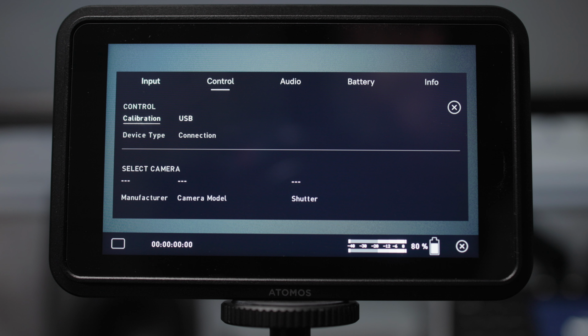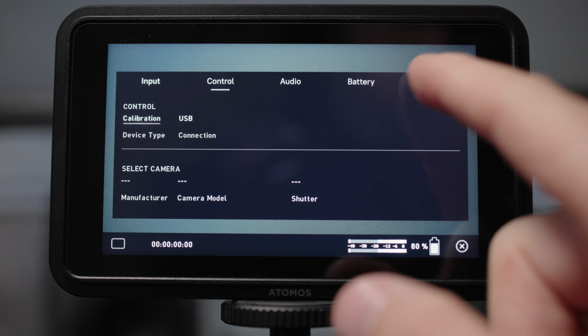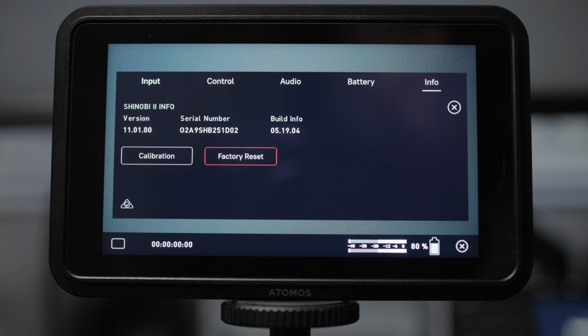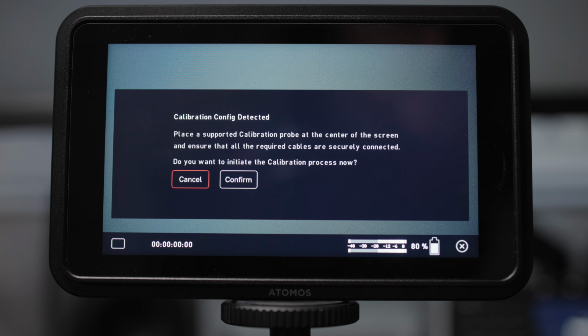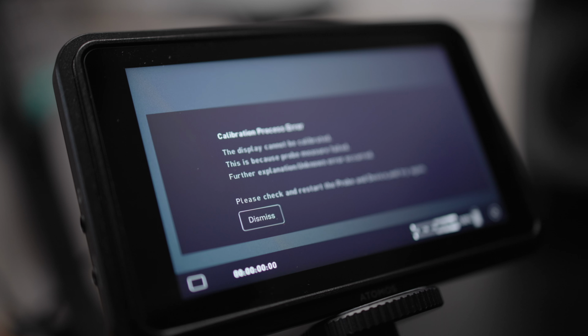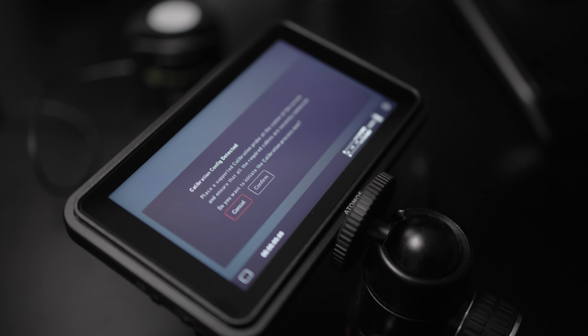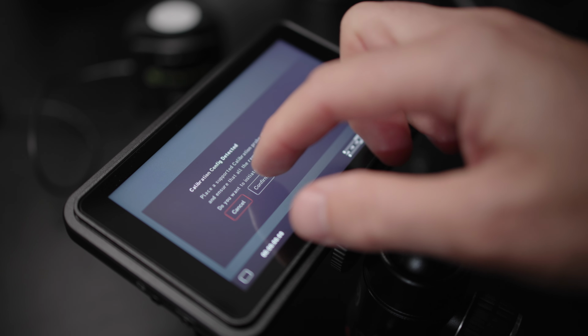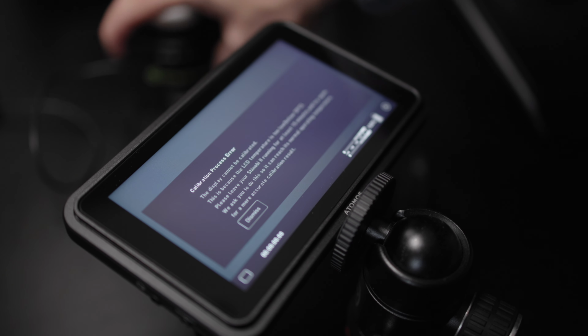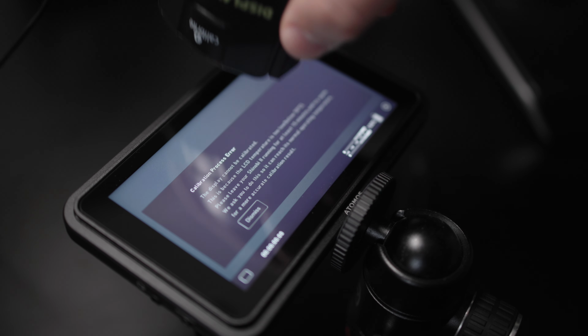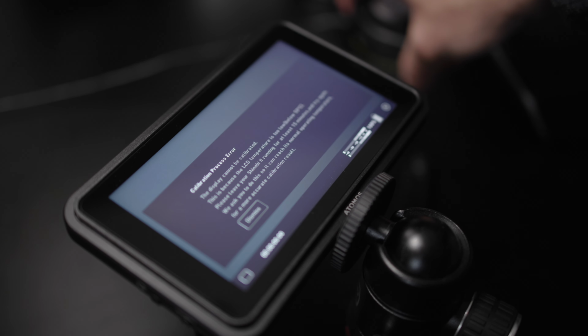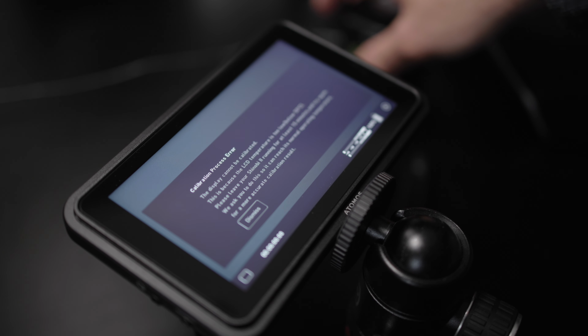To initiate the actual test pattern and begin that calibration process, come out of the control menu, go into the info menu and just tap the calibration button. If the probe isn't plugged in and you tap confirm, it will give you an error. It will say that it can't detect that there's a calibration device plugged in. Similarly, if you haven't allowed the monitor to get up to temperature yet, then it will also give you a process error. So it will say that the display cannot be calibrated because the LCD temperature is too low. So that's if it's below 50 degrees C.